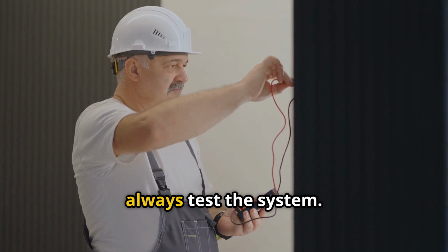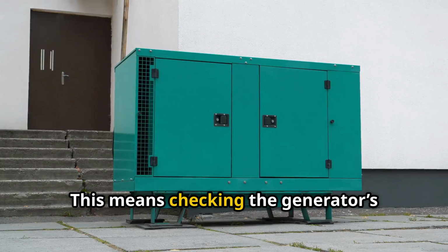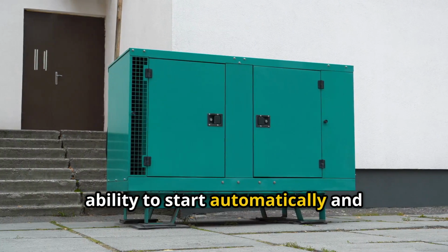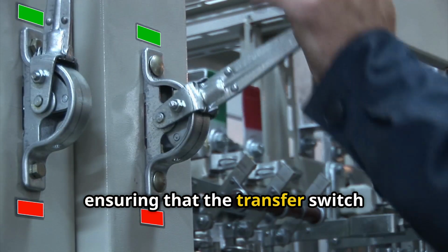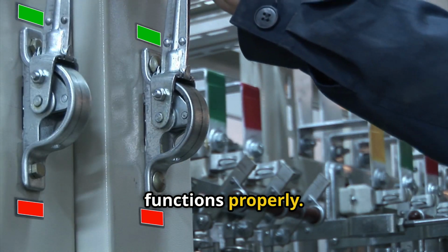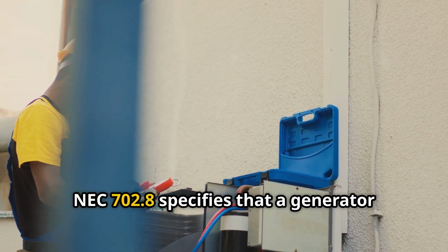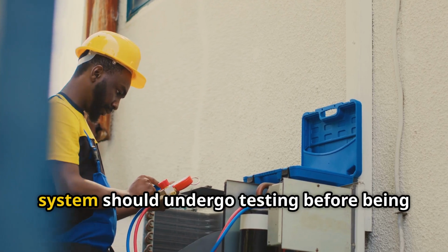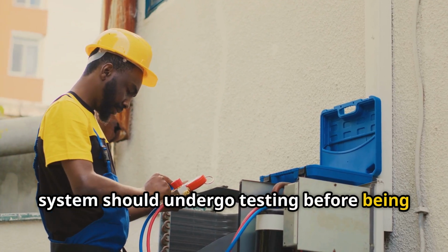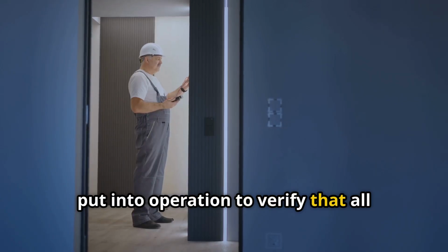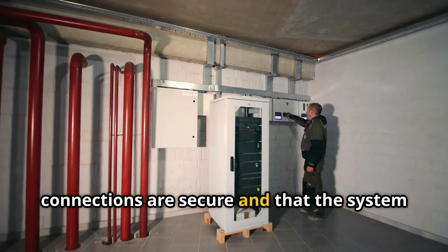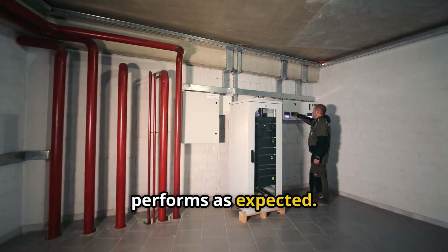Before finishing up, always test the system. This means checking the generator's ability to start automatically and ensuring that the transfer switch functions properly. NEC 702.8 specifies that a generator system should undergo testing before being put into operation to verify that all connections are secure and that the system performs as expected.